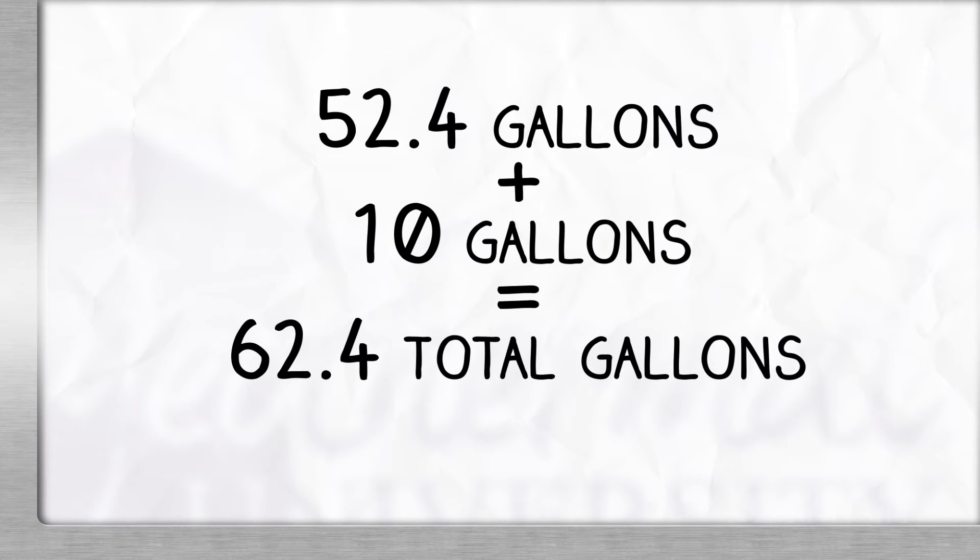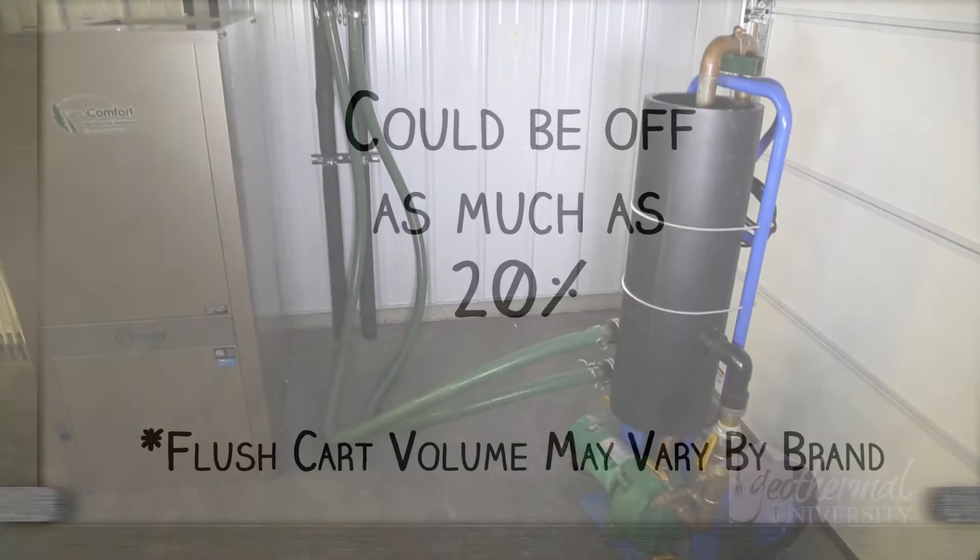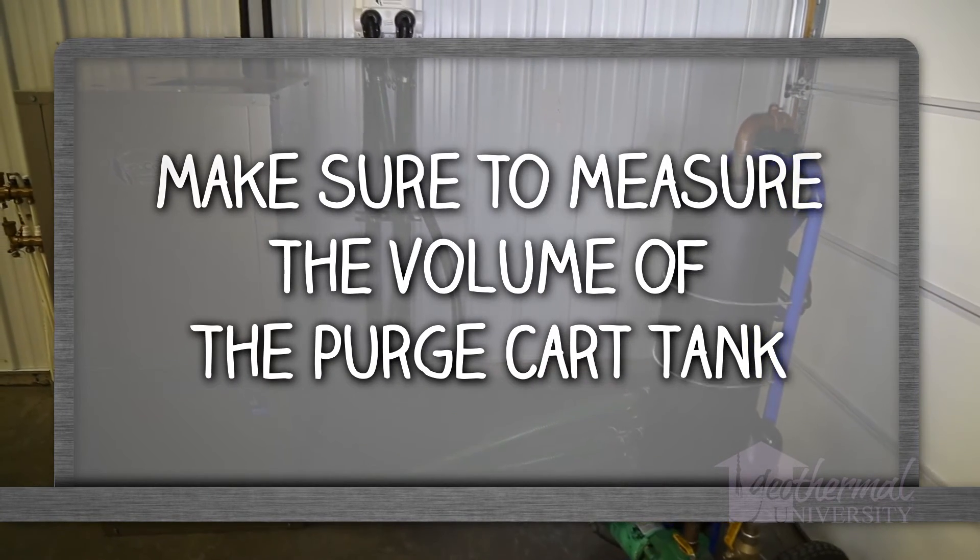So, our calculated number of gallons for purging of 52.4 gallons for the loop and system plus our tank on the flush cart. Otherwise, the protection level could be off by as much as 20%. To be precise, we recommend measuring the volume of the tank on your purge cart.